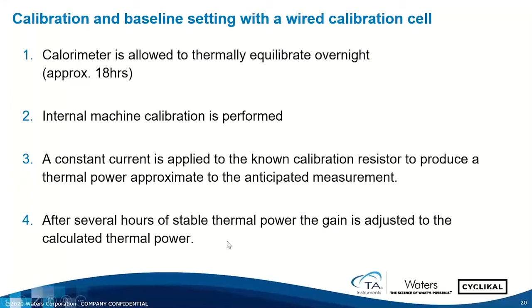That constant current is applied for a few hours until we get a stable thermal power from the calorimeter. After that thermal power is stabilized, we'll then adjust the gain through the device tab to equal the calculated thermal power. And the calculated thermal power, of course, is the current times the voltage. That typically tweaks the internal gain calibration constant a little bit. The internal gain calibration is pretty much the bulk of the calibration, but it's very important to do that tweaking of the thermal power to arrive at a very accurate gain calibration constant.